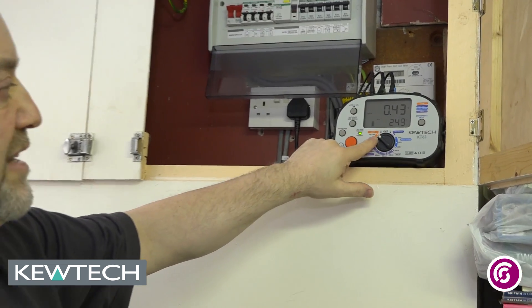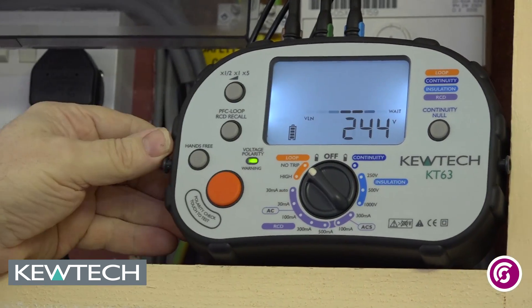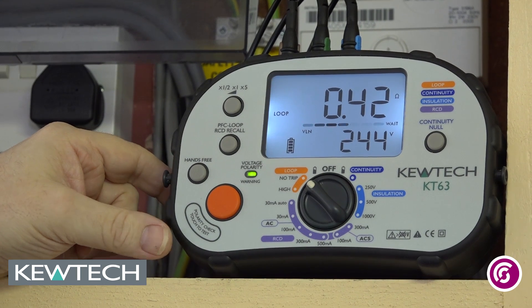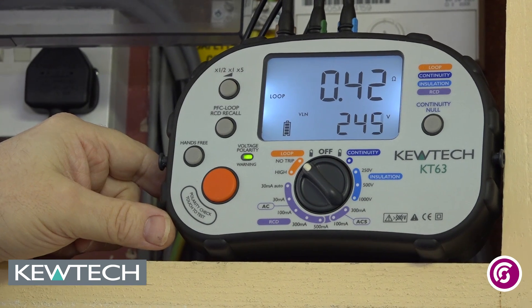So let's have a go. It is on the loop setting, no trip. We can see there we have got a voltage of 244 volts and we have done the loop and we have got a value of 0.42. You will see how fast that was as well — with a lot of these tests on the market you have to wait a long long time whilst it is conducting the test.